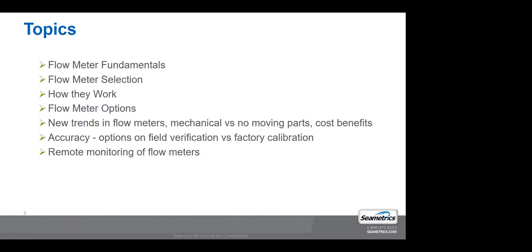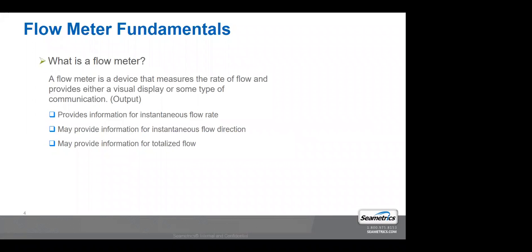For those of you that have meters, you might be challenged with accuracy testing them. How do I know my meter is performing accurately? And then we'll just touch on remote monitoring of flow meters. So what is a flow meter? It's basically a device that measures the rate of flow and provides a visual output or some type of communication.